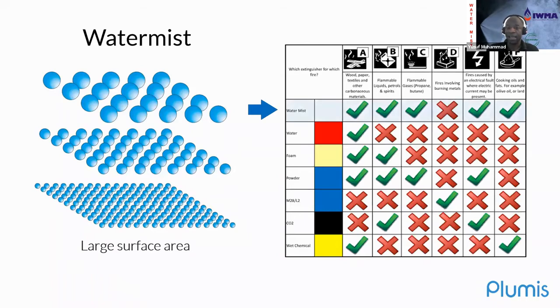And it is particularly powerful in this situation because it can be used on a broad range of fire types. So I mentioned earlier electrical fires, white goods fires, which are concealed. Because water mist is almost halfway between a wetting and a gaseous system, it has some traits that lend itself well to these kinds of modern domestic fires.